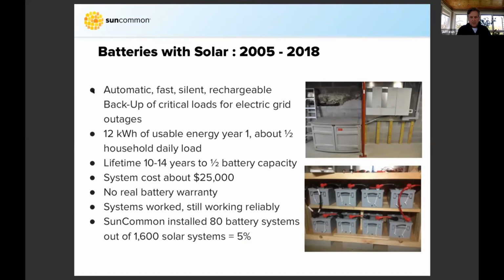A system like the one I showed would contain about 12 kilowatt hours of usable energy in its first year, about half of what an average home would use in a day. I say in the first year because the lead acid technology would degrade as soon as it started to be used. What we would tell people is that the lifetime of the system was about 10 to 14 years, and at that time the system would probably still work, but the batteries would only have half the capacity they originally had. These systems were not cheap.